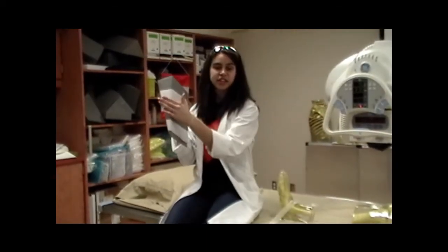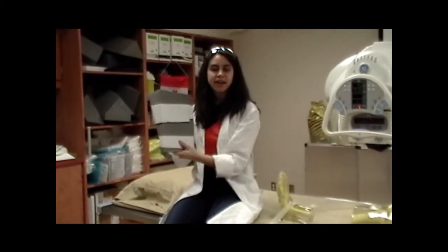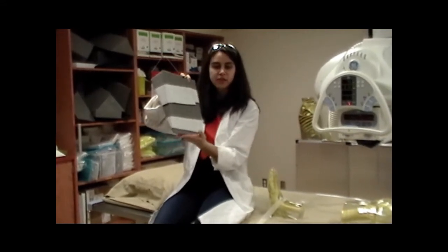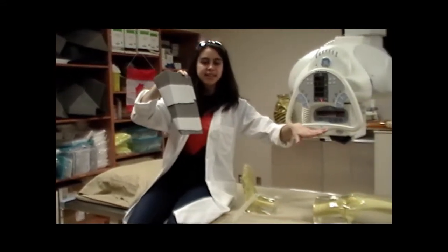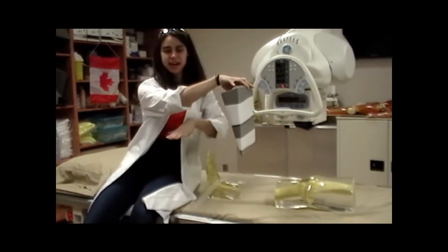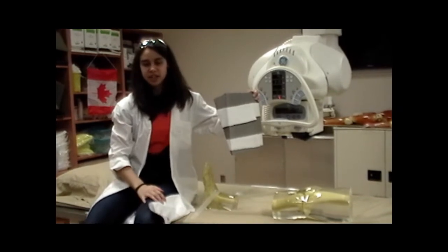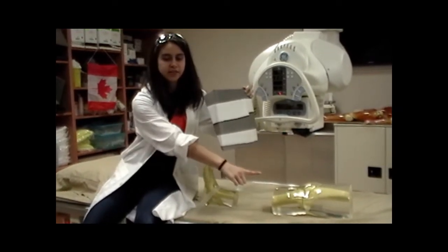Due to the angulation of one side of the anode, some X-ray energy gets dissipated by the heel of the anode. So the X-ray energy on the cathode side is more intense than that on the anode side. This is known as the anode heel effect. We can use this to our advantage and put the thicker part on the cathode side.